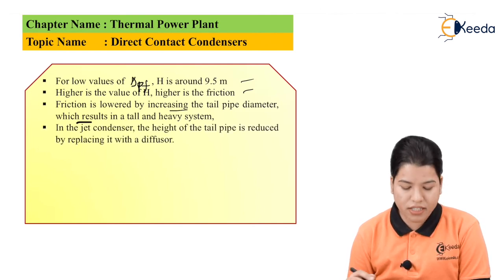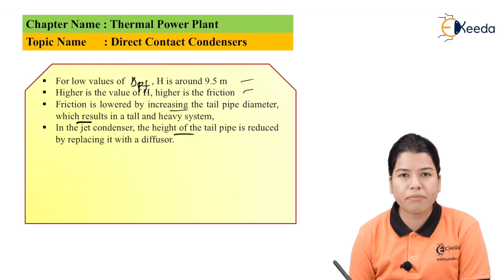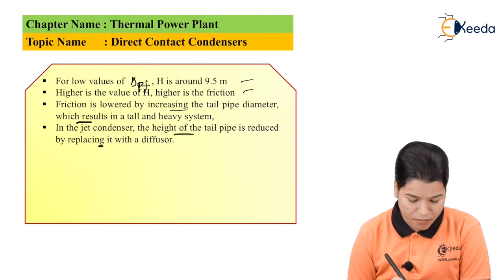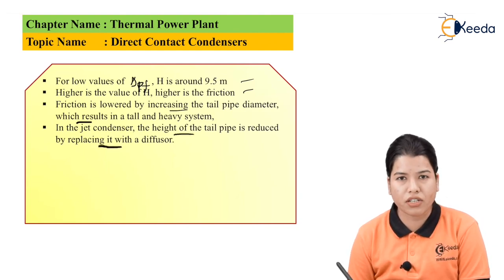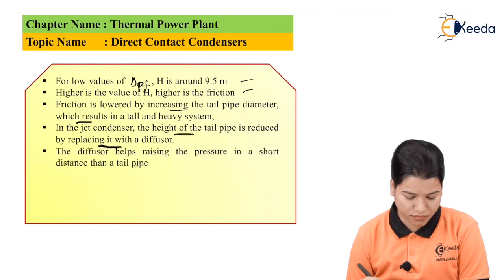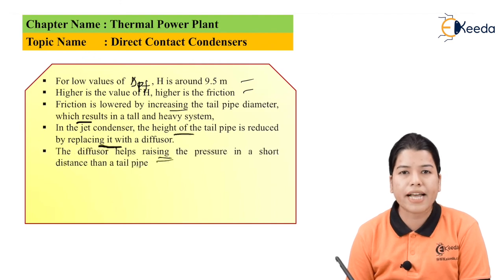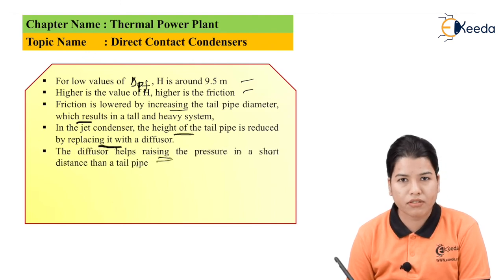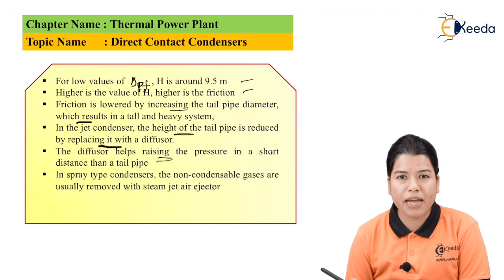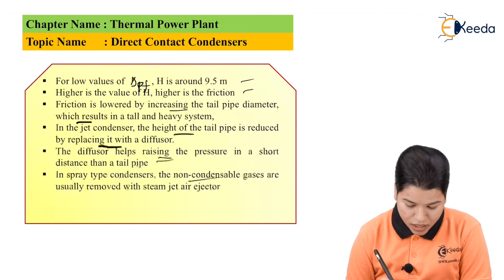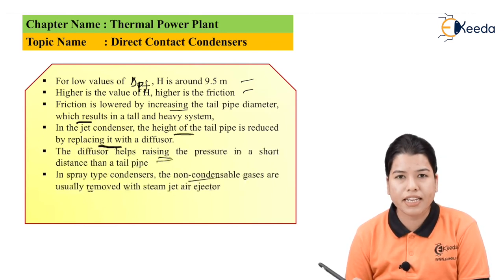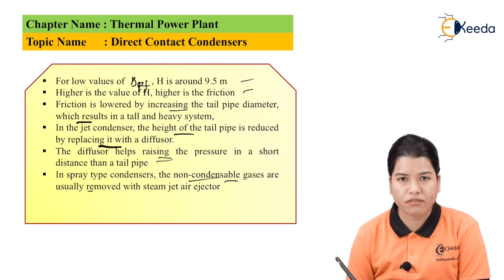In the jet condenser, the height of the tail pipe is reduced by replacing it with a diffuser, as shown in figure C. The diffuser helps raise the pressure over a short distance compared to the tail pipe. In spray type condensers, non-condensable gases are usually removed with a steam jet air ejector.